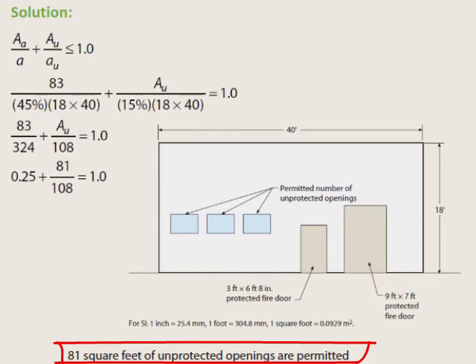As a further note, had 324 square feet of protected openings been specified, then the Unity Equation 7-1 would not have allowed any unprotected openings at all. The maximum areas for each type of opening in Table 705.8 assume that only one type of opening will be present. When both protected and unprotected openings are present, the sum of the actual areas of the openings over the permitted areas of the openings is limited to 1 per Equation 7-2. The maximum area of the...